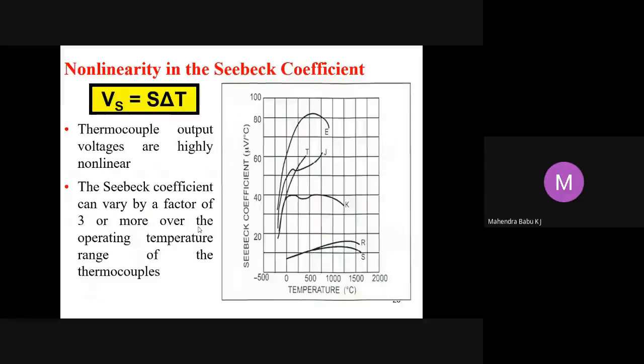It is not so easy because of the non-linearity in the Seebeck coefficient. Thermocouple output voltages are highly non-linear. The Seebeck coefficient can vary by a factor of 3 or more over the operating temperature range of a thermocouple. Here you can see the plot of Seebeck coefficient versus temperature, which is highly non-linear.